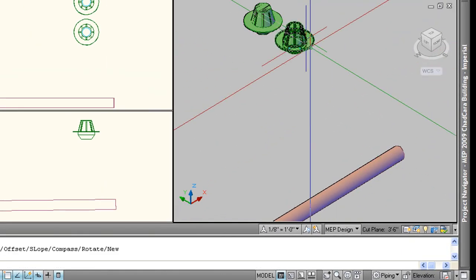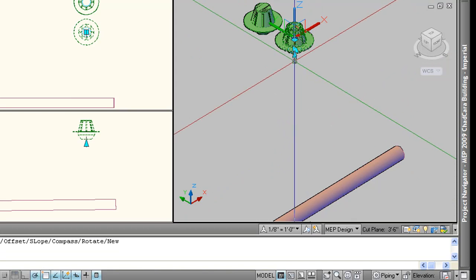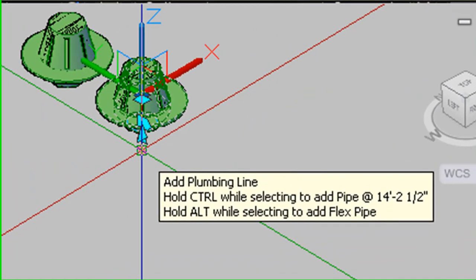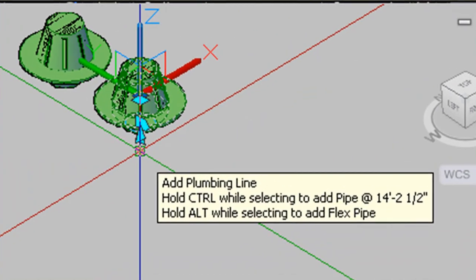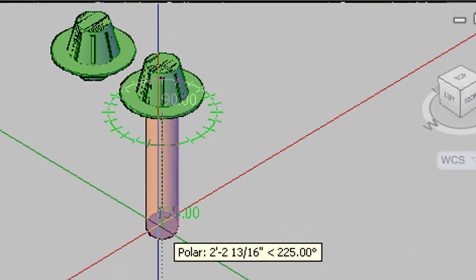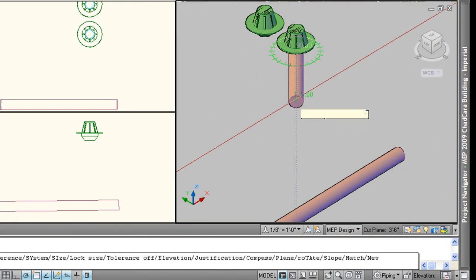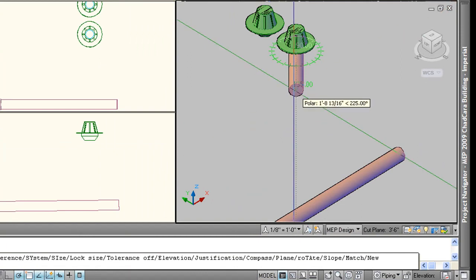Go back to the roof drain, select it again, and this time just hover over the pipe add grip and slow down to read the flyout. Read these flyouts. They will help give you the clues that you need. In this case, we see that this particular piece of content is defaulted to add a plumbing line first. Whereas if we just hold the control key down while selecting, we'll get our pipe. Or we can hold alt while selecting to add flex pipe. So let's do that. Hold control key down and lo and behold, I get piping. So we resolved that problem using the flyout as a clue.